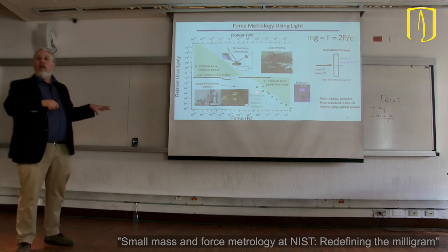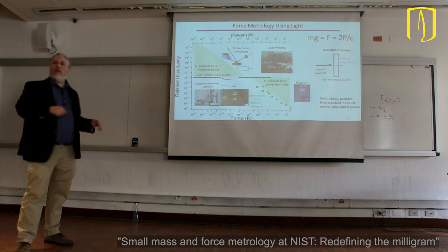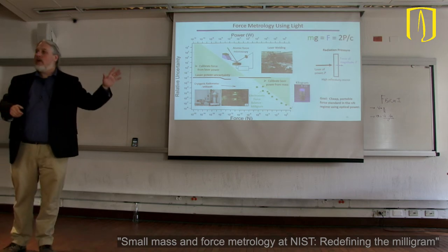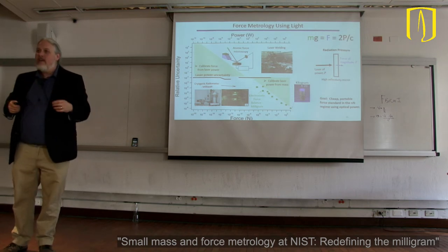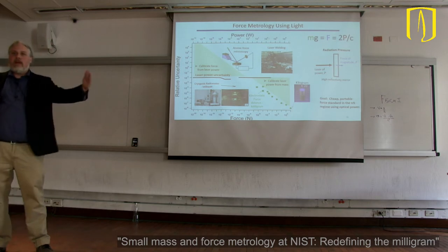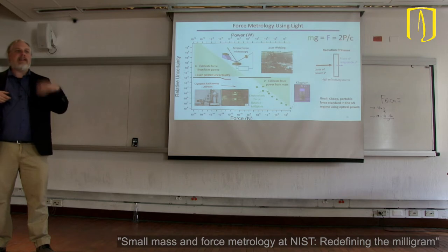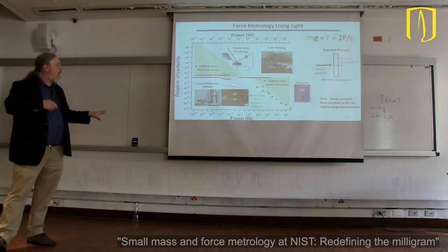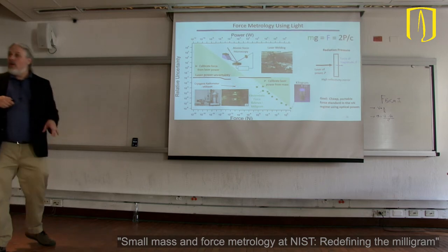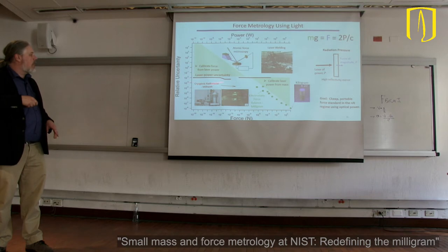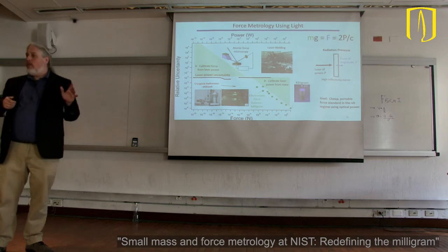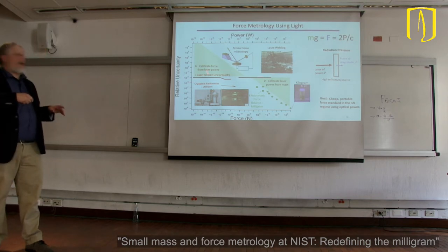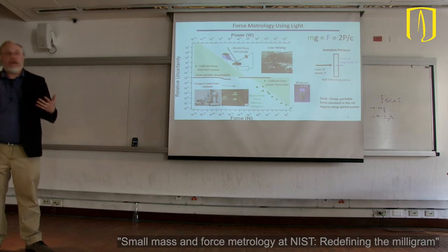In this area, laser power metrology comes from an instrument called the cryogenic radiometer. It's a big calorimeter, it measures heat. When you shine the laser, it absorbs the laser and measures the heat from the absorption, and that tells you the power. This is not too bad, actually, but only over a very small range of power. At about 1 milliwatt, the uncertainty in this measurement is parts in 10^4. Everywhere else, it's about 1% uncertainty.